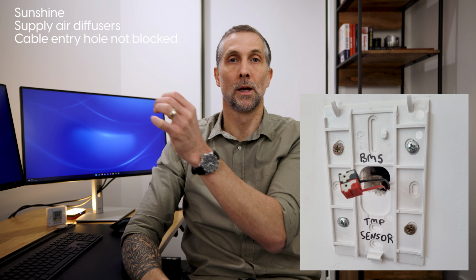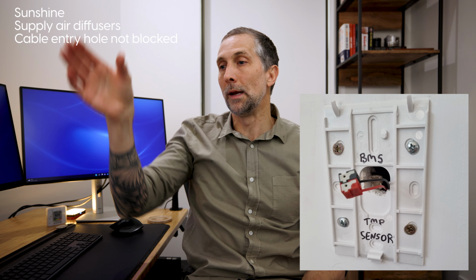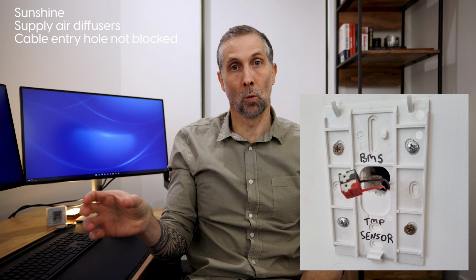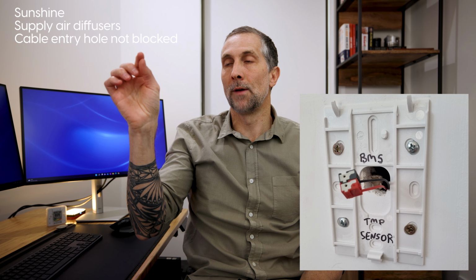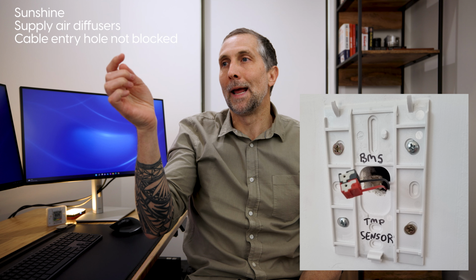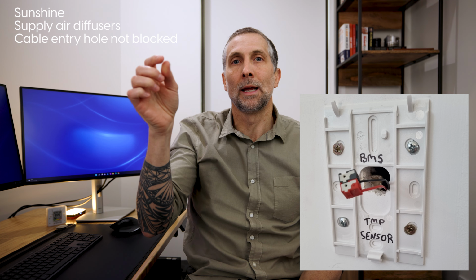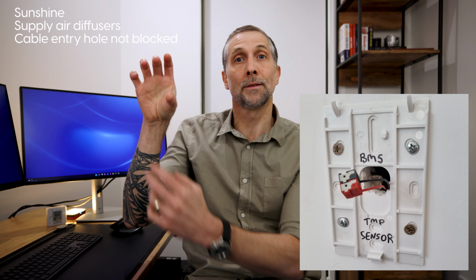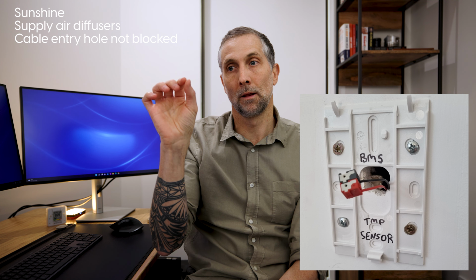My favorite one, where the plasterboard wall that the cable runs down, you drill a hole and you pull the cable through and you install the sensor on there. Most times when I do an inspection, that hole has not been blocked with silicon, which means that that void in the wall, in the plasterboard wall, the dry wall, if that hole's not blocked, a little bit of air can drift through there into the sensor housing and affect the temperature reading.